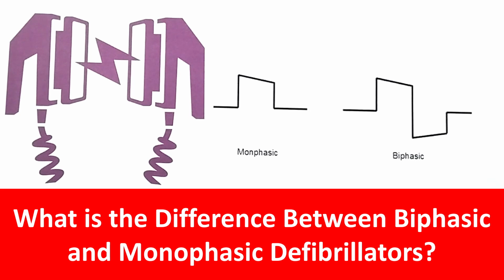If you have checked older defibrillators which are monophasic, you would have seen that they have a maximum energy of around 360 joules. While most of the modern defibrillators, which are biphasic, have maximum energy around 200 joules compared to the 360 joules. There are some biphasic defibrillators giving higher shocks also, because sometimes resistant fibrillation may require higher energy shocks.